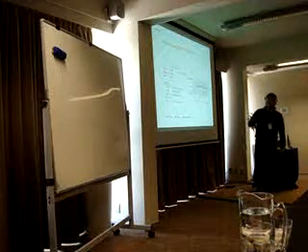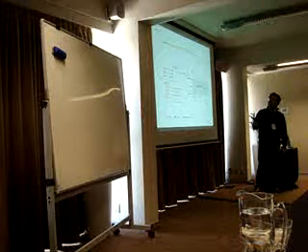So basically, for the standard, this is the point I want to make now. The standard is actually very informal, and they supply a hardware-oriented implementation. Usually, this is the first information you get from the standard, which is the declaration of the function block. In this case, we have the hysteresis function block. It has three inputs, input 1, input 2, and the hysteresis band, and all of them are real numbers. And this is the output Q of type Boolean, which means should you trip the alarm or not.